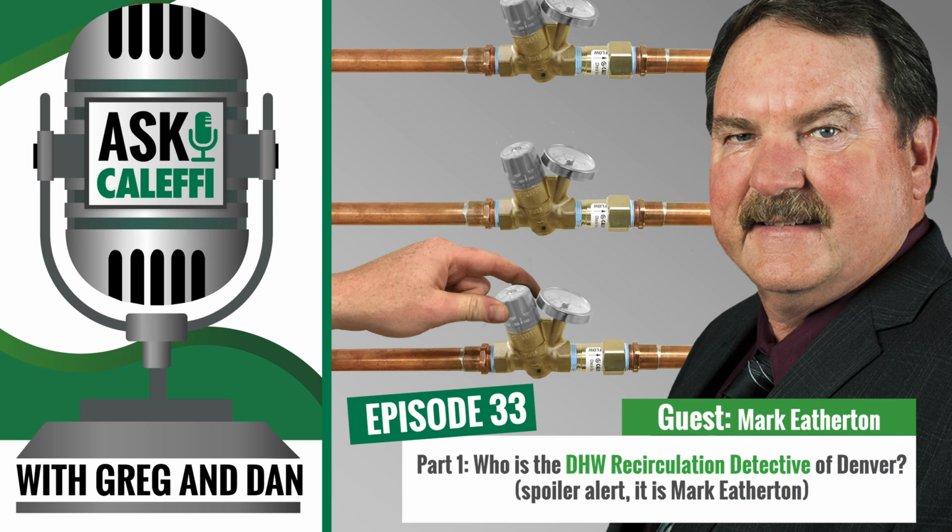Right, and you basically have to tell it what you want it to do and when you want it to do it. Sure. So by putting these thermal balancing valves in here, you basically straighten the system out completely. It eliminates excess flow rates and erosion. It won't reverse the damage that's already been done, but it will stop any more damage going forward, and gets rid of all those complaints of people complaining.